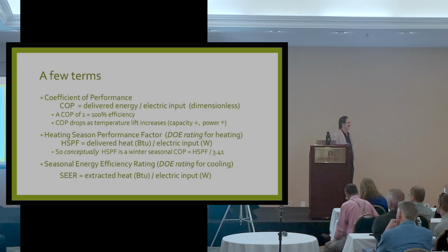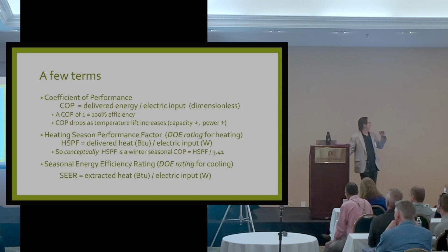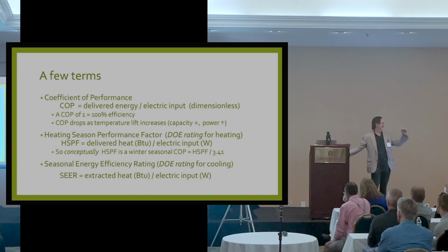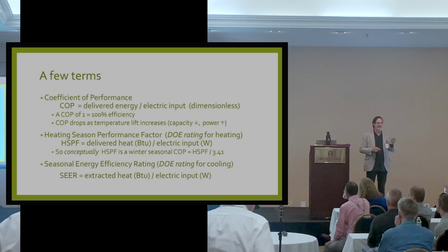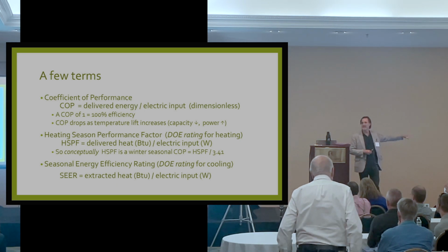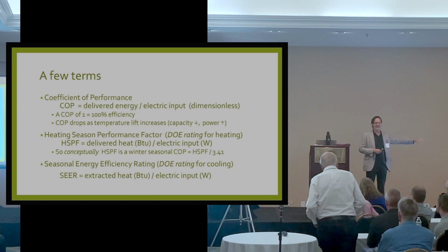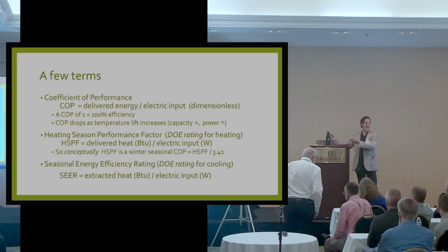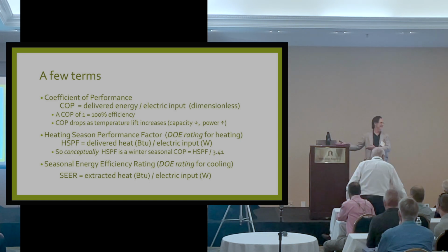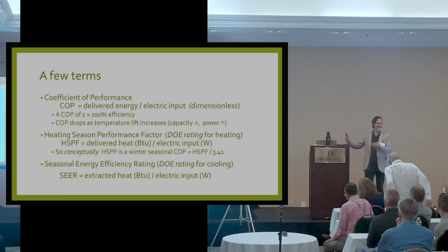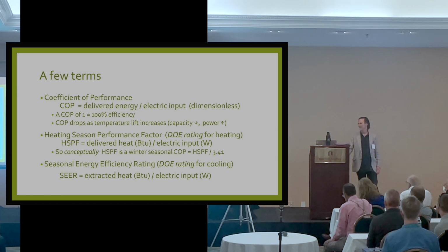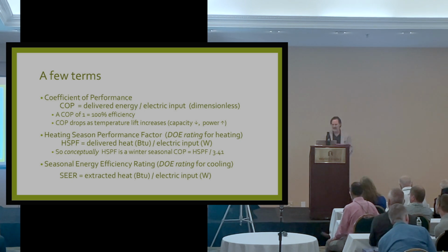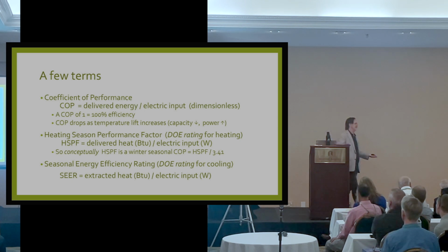And I'm not saying divided by the energy input. I'm saying divided by the electric input, because of conservation of energy, all of the heat that goes into the building comes from somewhere, and some of it comes from outdoors for free, and you don't count that in the denominator. If you did, you would have 100%. It would always be the same amount in the numerator and the denominator. So if I have a COP of 1, that's 100% efficiency.